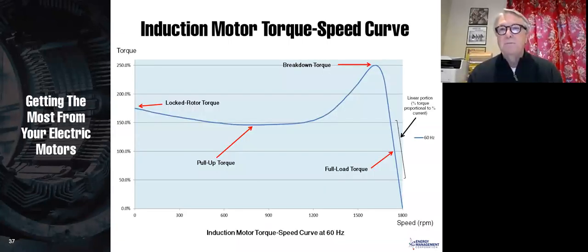As you come up to speed, this is the induction torque speed curve. You'll notice on a normal induction motor, we might start at 150, 175, 200, 250, depending on the motor, locked rotor torque. Then it decreases a little bit to our pull-up torque value, then it gets to your breakdown torque, and then finally up to our full load.